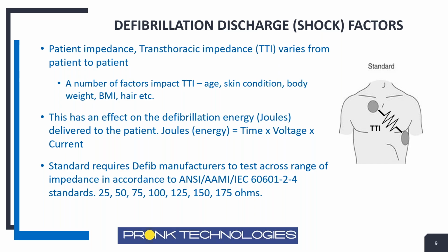And what it requires is that you test the defibrillator across a wide range of impedances, trying to simulate the wide range of patients out there in their transthoracic impedance, to make sure that it will fire within its spec across that wide range. And in some of the service manuals, you'll see there are charts that say, okay, if you're testing at impedance A, this is what your energy delivery should be. If you're delivering at impedance B, your energy delivery should be within this tolerance. So there are charts and tables in the service manual that lay out what the expected results should be across those wide impedance ranges.